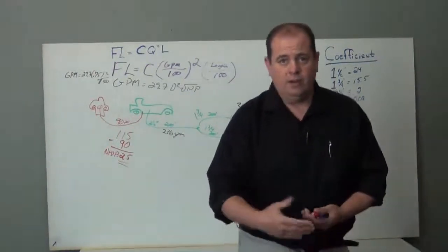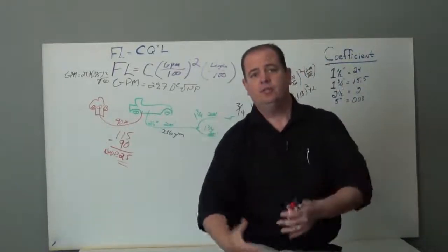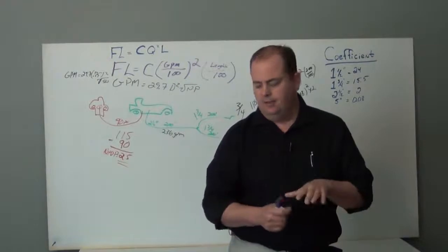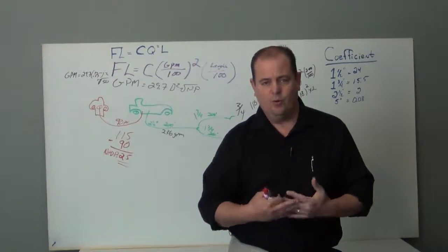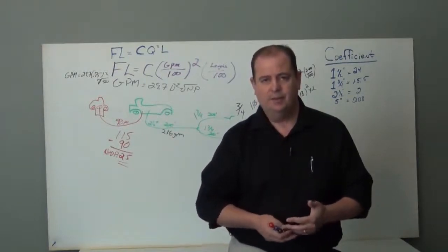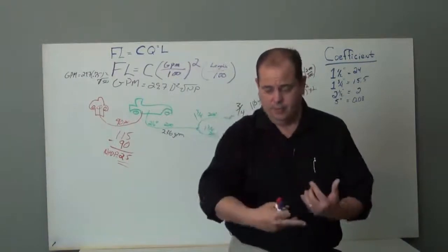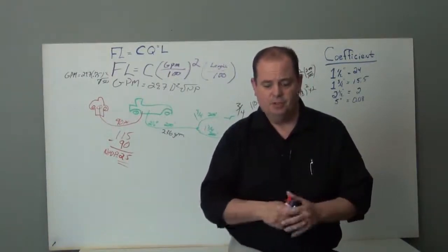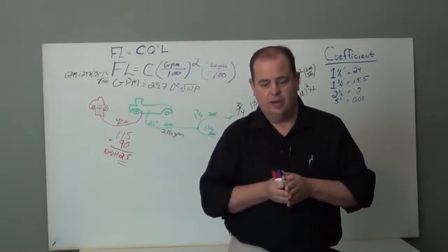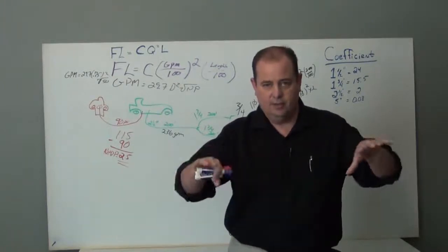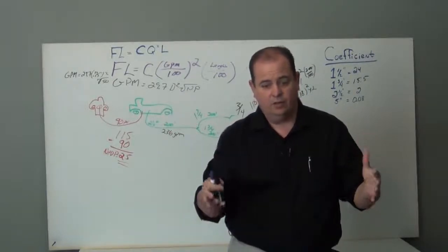So one other thought to think about, it's kind of old school, you don't see it much, but two-stage pumps, for example. Years ago, people tried to explain a two-stage pump to me, and they always gave me misinformation. What you've got to think about is two impellers, two pumps on the same shaft, spinning at the same RPMs, creating the same amount of pressure. A two-stage pump will do one of two things. It'll either split the water in half, and the water goes to each impeller, then comes back together and goes out, which is known as running parallel or volume.